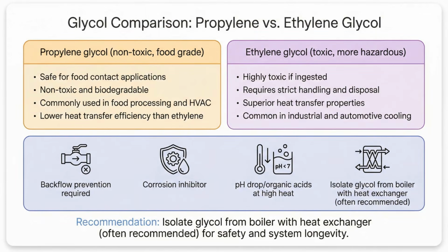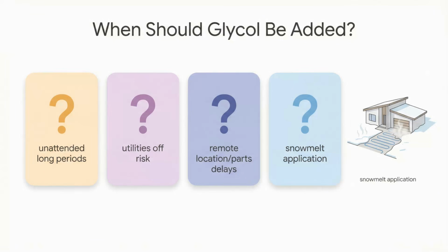Glycol is used for freeze protection, often in slab-on-grade or snowmelt applications, but it comes with trade-offs. Propylene glycol is non-toxic and generally preferred where cross-contamination risk exists, while ethylene glycol is highly toxic and can be more corrosive at high temperatures. Any glycol system still requires backflow protection, and under high heat, glycol can break down, forming organic acids that lower pH, so inhibitors are needed. Many recommendations suggest isolating glycol from the boiler using a separate heat exchanger to reduce damage risk. Glycol should be added only when freeze protection is actually needed.